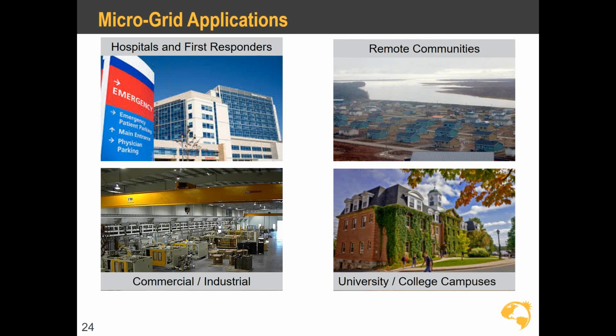Hospitals are already installing traditional generators. A traditional generator has no payback - it just sits there waiting for a power outage. With a CHP unit, there's a payback depending on your heating load, and you're able to use it as the generator when needed as well.